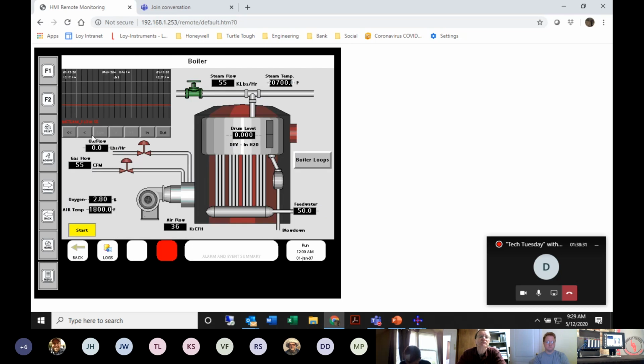We do have other graphics, like boilers. So here's a typical graphic of a boiler. A lot of these widgets that you see on the display are chosen from a library of standard displays that you can build with the HC900 operator interface. You can impose a lot of the digital and analog signals out onto the screen so you can see actual process data as you're doing your control.